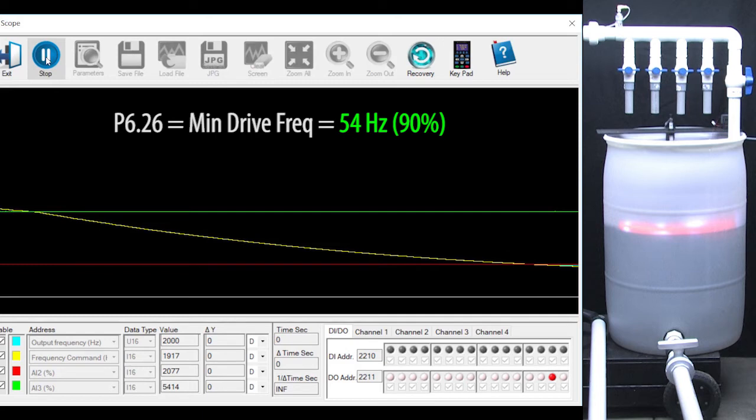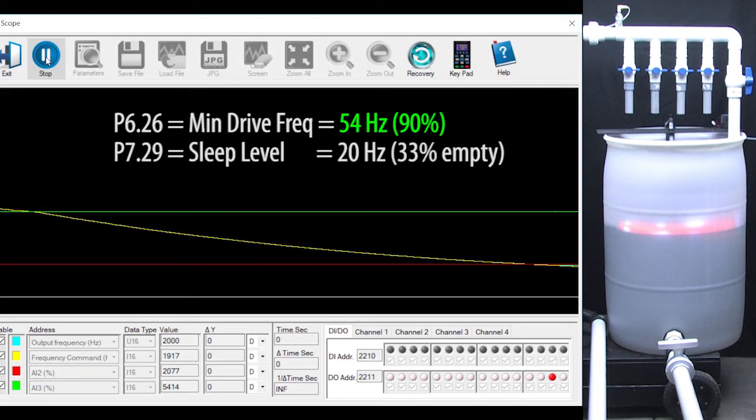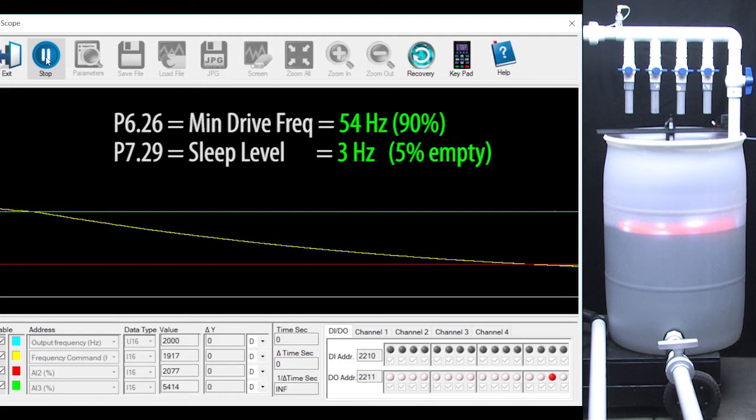That takes care of speeding up the tank filling operation because we are forcing the motor to go fast most of the time. And since the new min motor speed is nowhere near cavitation, we can also set the sleep level to whatever level we want. I'll set that to 5% which is 3 Hz. And that takes care of issue number 2, filling the tank to whatever level we want.